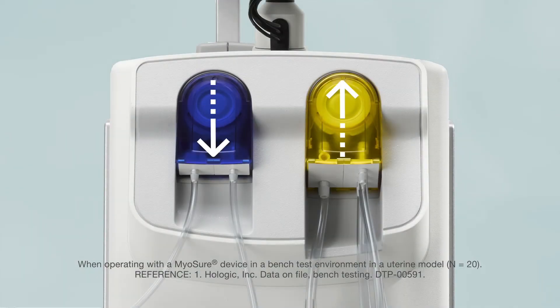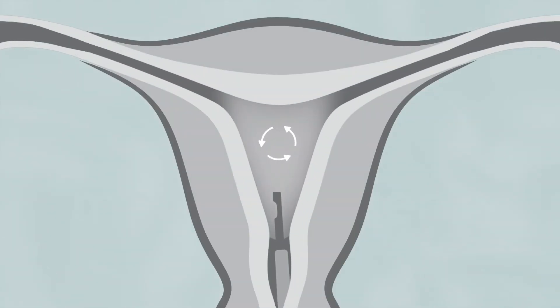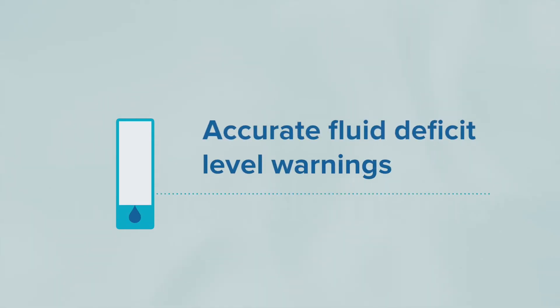While using the Myosure system, FloPak technology maintains the average intrauterine pressure within 1%. This consistent pressure reduces pulsing as the Myosure system starts to run. Accurate fluid deficit monitoring helps inform clinicians by providing warnings when the deficit level reaches 75% of the set limit.